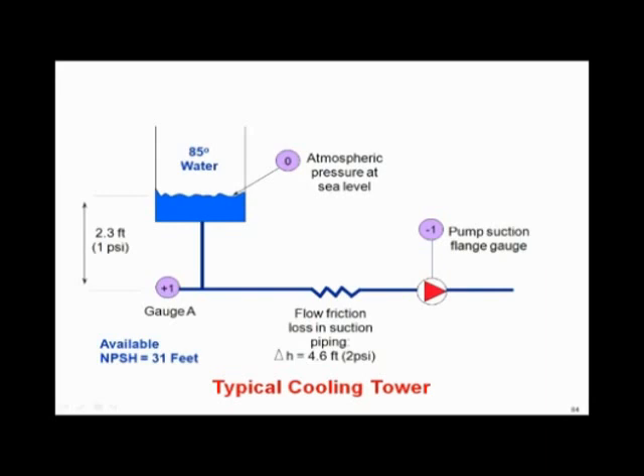Well, if it's not a compound gauge and you've got a negative pressure, how are we going to know it? So first pet peeve, make sure. So this would not be an unusual situation, would it? Does this cooling tower at Myrtle Beach, does it have an NPSH problem? It does not. Slightly negative pressure, you may get a little air out of solution, but remember you're pumping 85 degree water. So what would it take for 85 degree water to boil? Take a real negative pressure, negative one pound, it's not going to make 85 degree water boil. Probably a negative 13 pounds, 14 pounds, that ballpark, to get 85 degree water to boil. Bottom line, the available NPSH is 31 feet. There's really nothing wrong with this application. I don't like the negative pressure, but it's not unusual. This is a typical cooling tower, no NPSH problem at all.